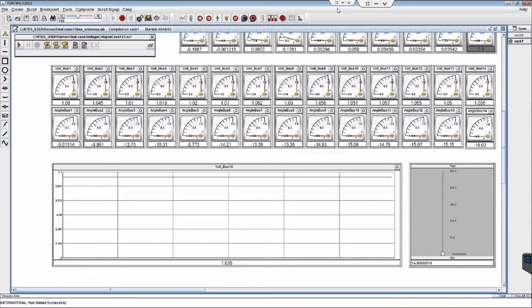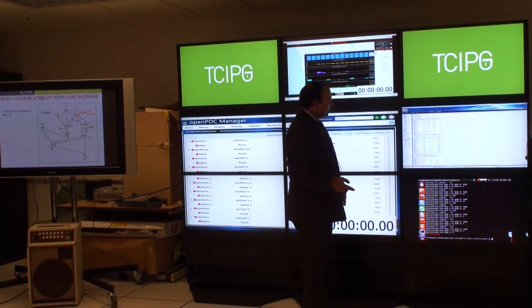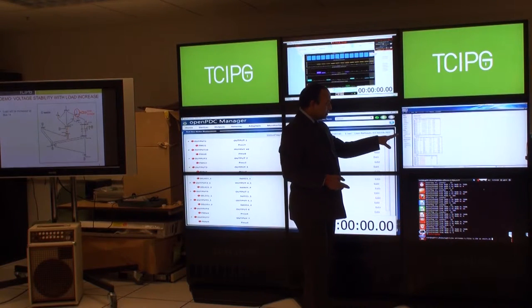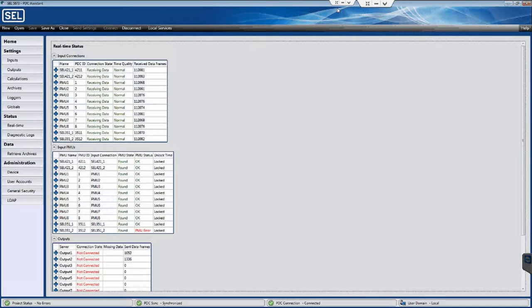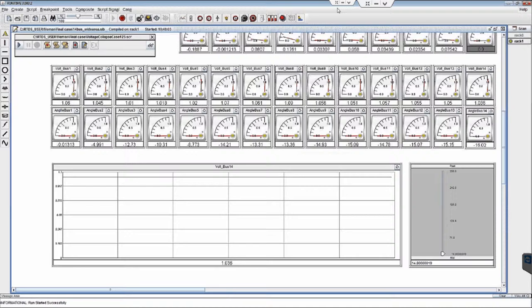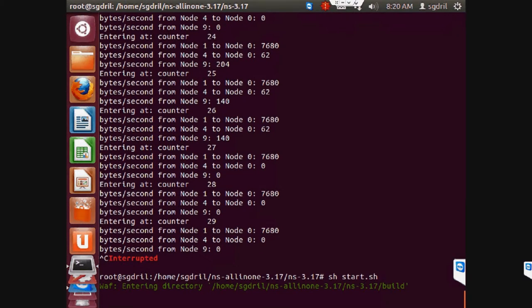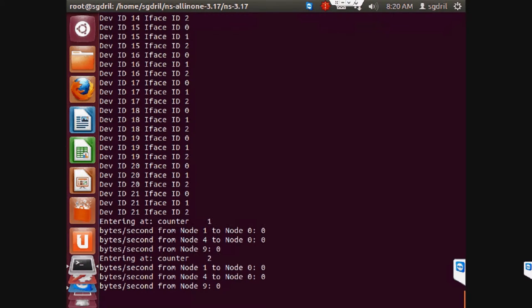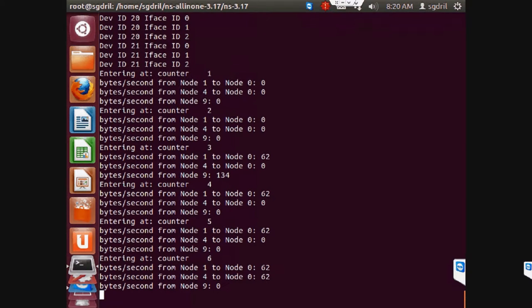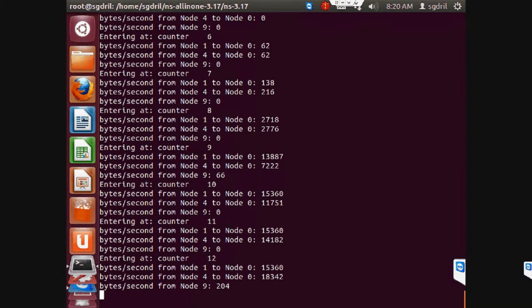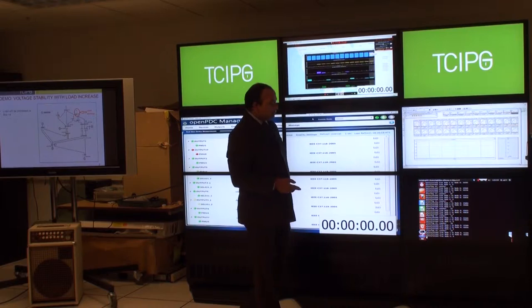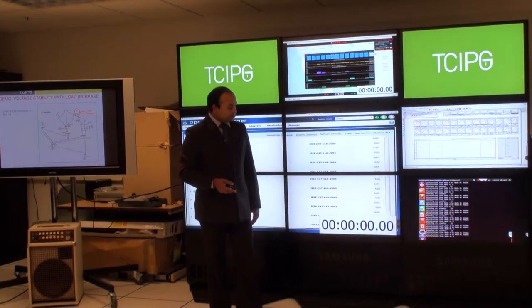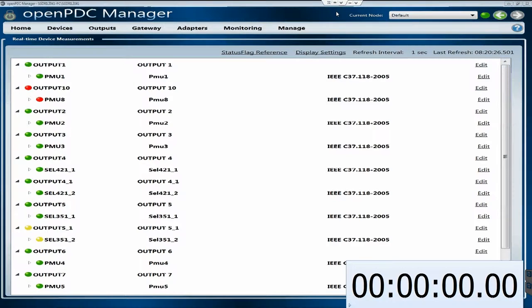We talked about physical system. Now if it's up and running, you'll see the PMU data getting to the substation PDC. You see that all the PDCs, which is SEL PDC at the substation, are receiving the data and operating in normal mode. From here, the data will go through to NS3. We'll initialize our NS3 and you'll see that all the data is being transferred from substation PDC to control center. This has been initialized and you see that number changing, those are data packets. Those are specifically chosen to show only those nodes which you want to show because that's where we will model the outage or denial of service attack. You see all this are turning from red to green, which means that now it's all up and running.